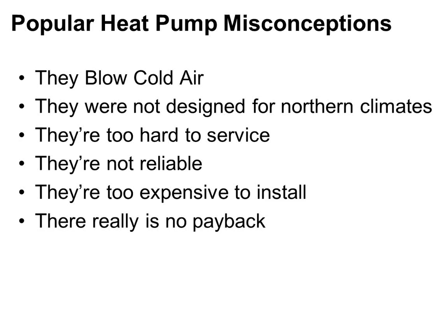There's been some concern perhaps about the expense of installing a heat pump. A heat pump takes no more effort to install than an air conditioner. Right? It's the exact same thing, exact same piping, exact same everything. So that's another misconception. And then there's the payback scenario, that there is no payback. That may be true sometimes. It's not true other times. I'll give you specific examples of when paybacks are going to work and when there are going to be no paybacks, and you should not use a heat pump. So we'll go through that a little bit.